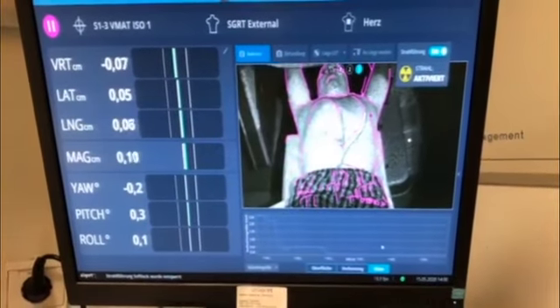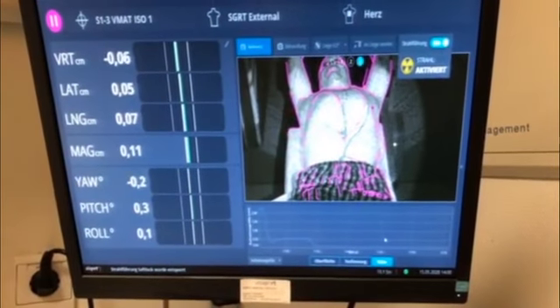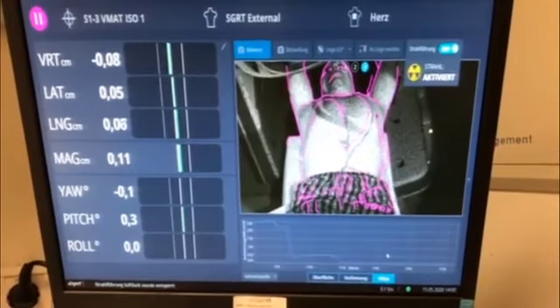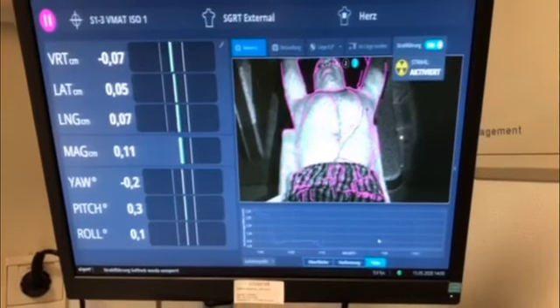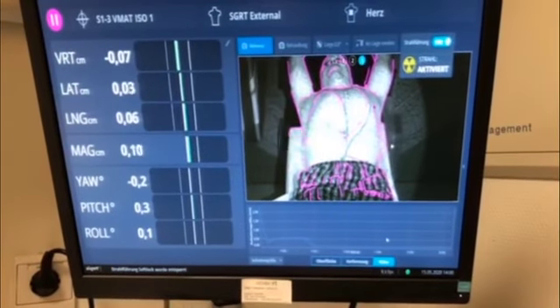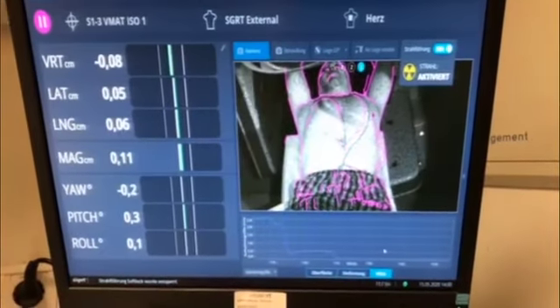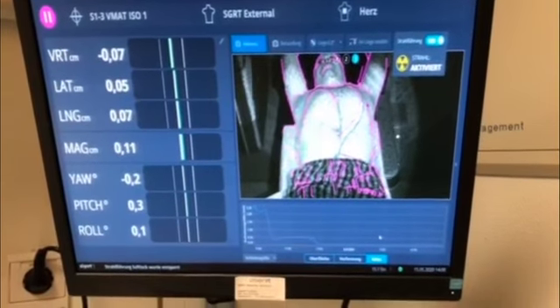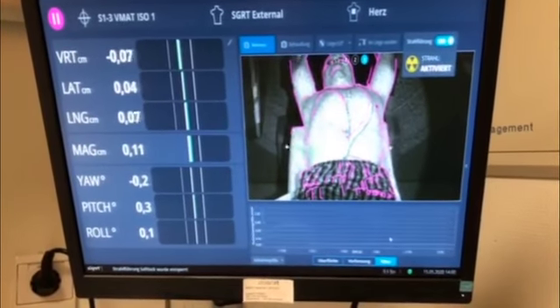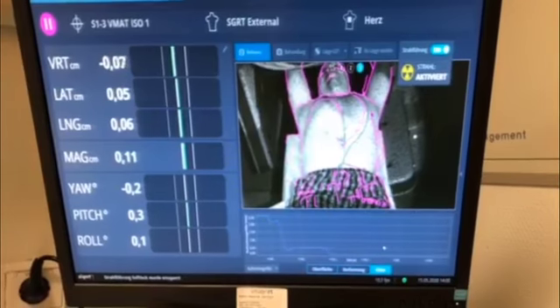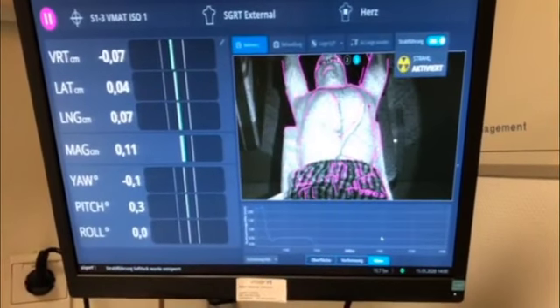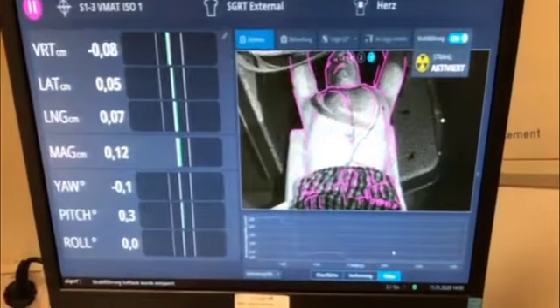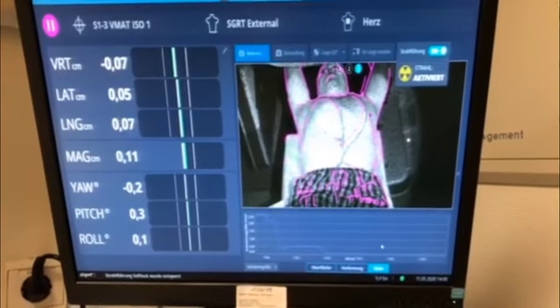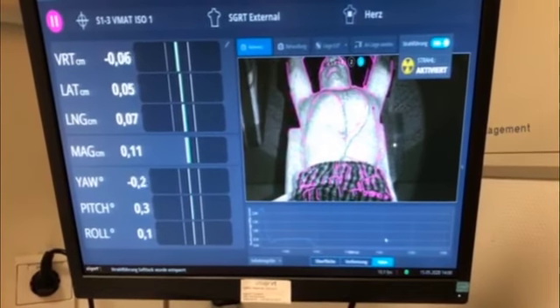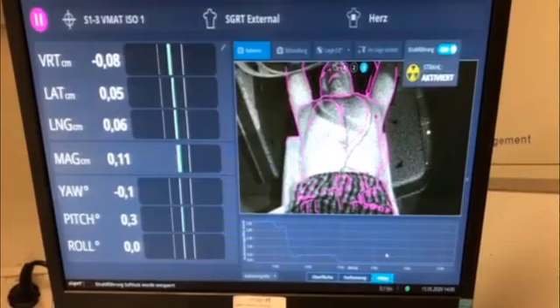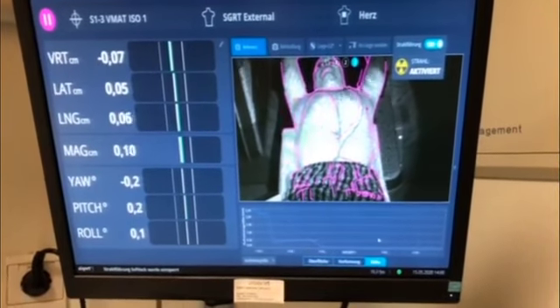This is an example of the treatment where you can see, because of the video function from Align RT, quite well the patient positioning. You can monitor the patient during the entire treatment, and if there is any issue, you can easily detect it and stop the treatment. Anyway, the LINAC is connected with Align RT, and the LINAC also stops if the patient moves. Simultaneously, it is important to mention that we have another monitor always showing the electrocardiography signal.